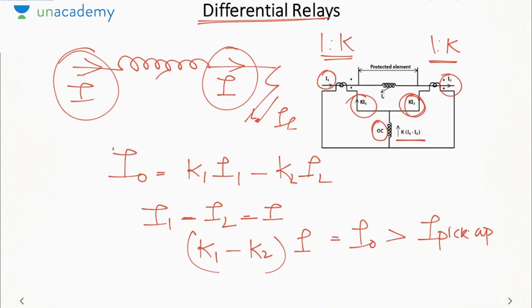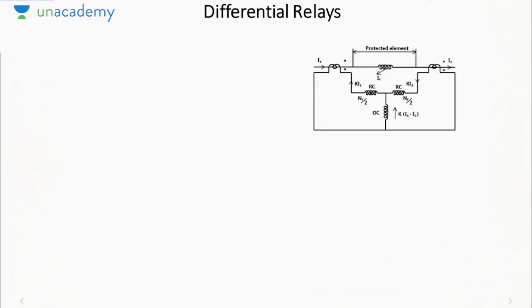This can be due to a manufacturing defect, or it can also be due to saturation, because if any current transformer saturates, then its secondary current will remain fixed while the primary current may change. So if one of the transformers saturates, then their transformation ratio will change. Hence, there will be a mal-operation of the relay. So that means we have to make certain changes in this relay to make it more reliable and to remove these problems of saturation or mal-operation of the relay. So we move to a circuit called the percentage differential relay.